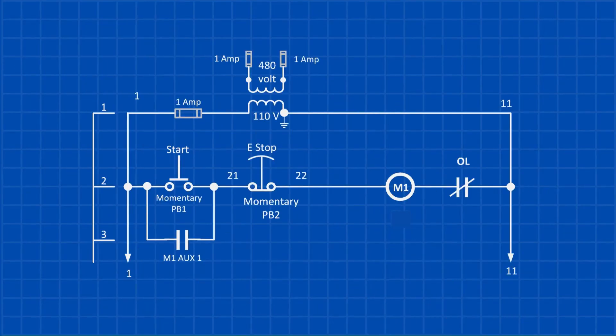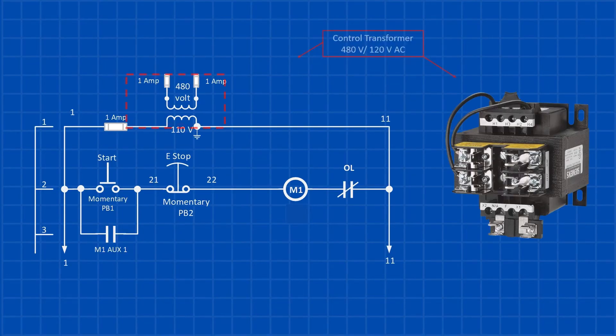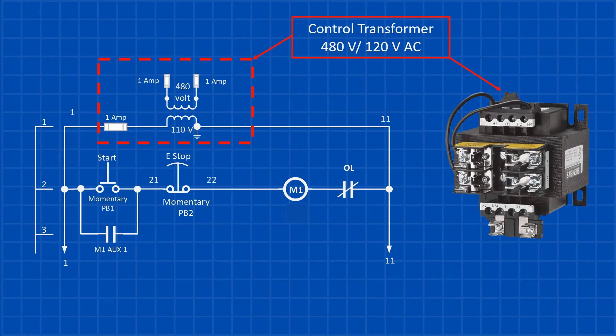Now let's take a look at the control circuit for our 30-horsepower motor. In its simplest form, the motor control circuit will look like this. The first component in our control circuit is the control transformer, which has primary and secondary fuses. It steps down the voltage from 480 volts to 120 volts AC, supplying power to the entire control circuit.